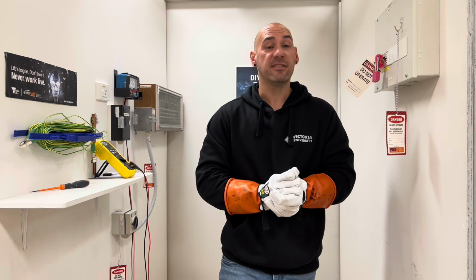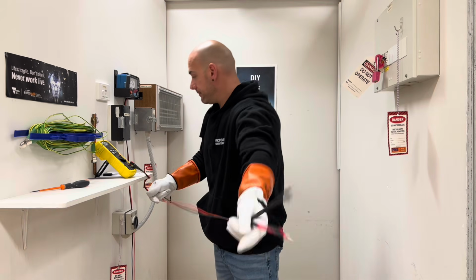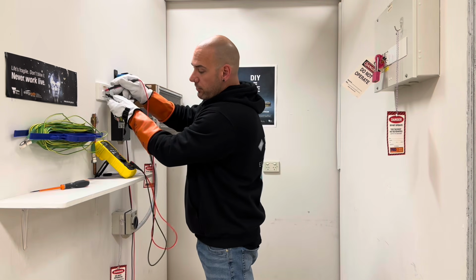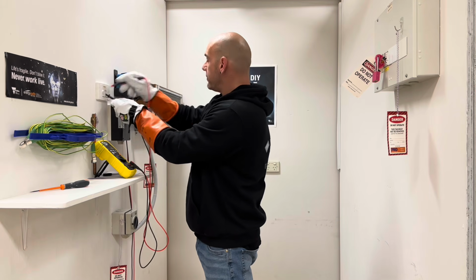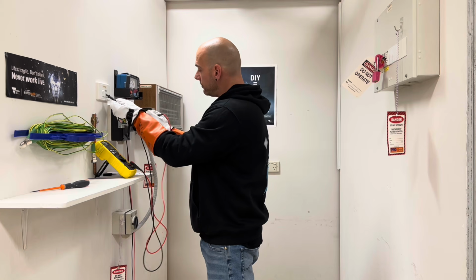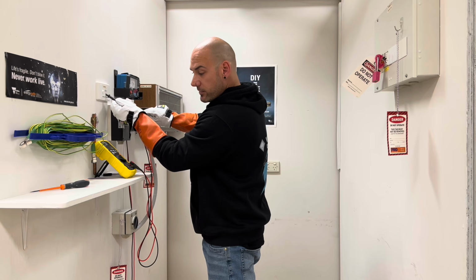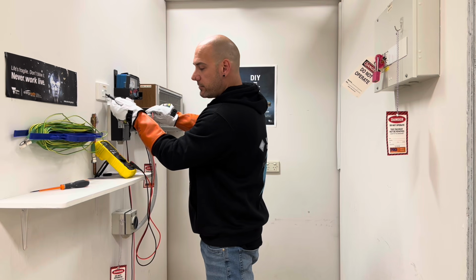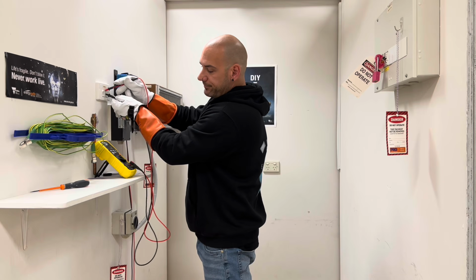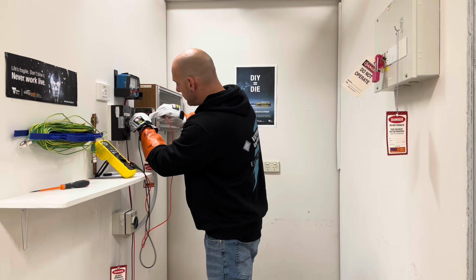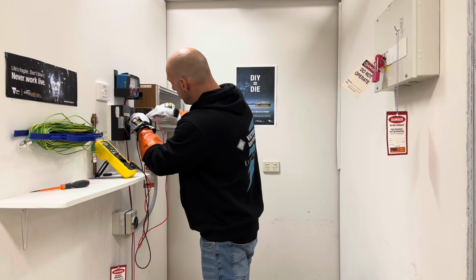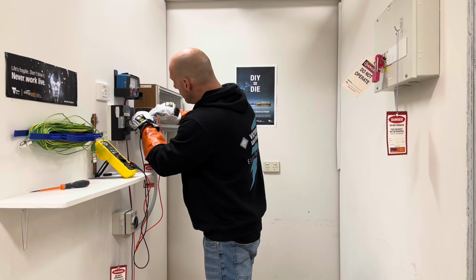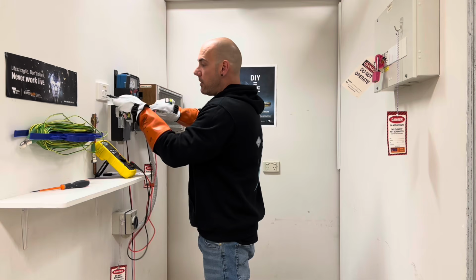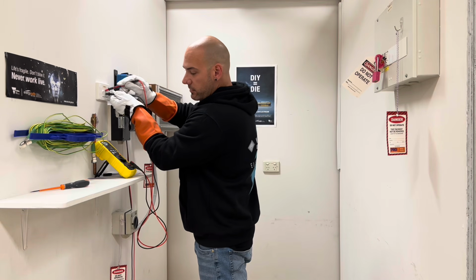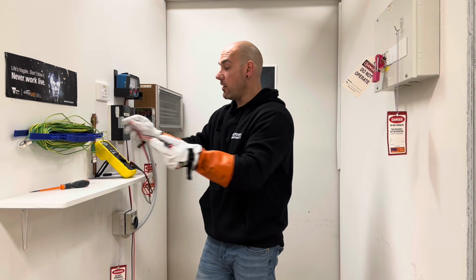We then can go back to the appliance and see if we've isolated the correct circuit. We test our voltage meter and we have 24 volts. Then we go to the terminals and we test from earth to earth, 0 volts, earth to neutral, 0 volts, earth to active, 0 volts, which is good. We test our tester, it's working, 24 volts, and we'll just test between conductors. Earth to neutral, 0 volts, earth to active, 0 volts, neutral to active, 0 volts, and we test our tester at 24 volts. So at this point, I would say we've correctly isolated that circuit.